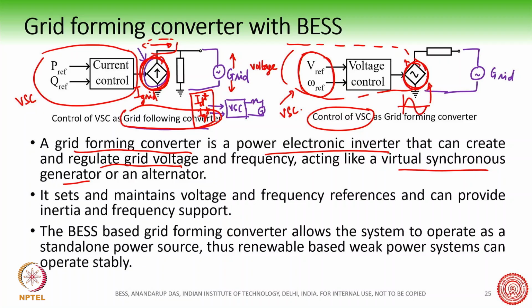This will be the reference for this converter, and this is called the grid forming converter. Why is it grid forming? Because the voltage source converter is behaving like a voltage source having its own amplitude, frequency, and angle. So it acts as if it were a new controllable synchronous machine added to the grid. Remember, the grid is made up of several synchronous machines plus renewables.